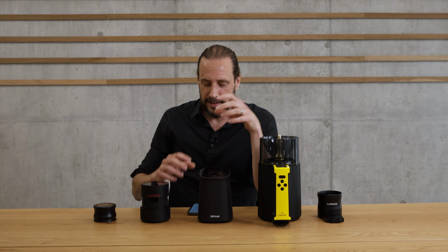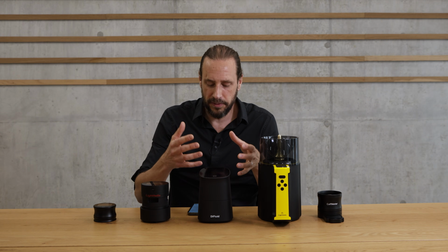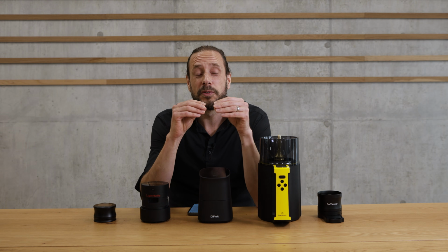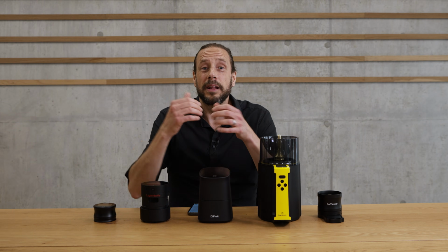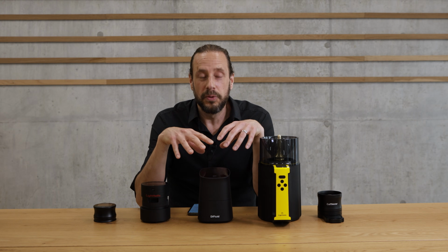What is happening here is that inside the sealed chamber, there is a small polished mirror, and an electrical cooling element chills this mirror down until water vapor builds little vapor spots on the surface, and an optical sensor measures that. Imagine cooling down a glass of water: at one point you get condensation on the outside. This happens with this mirror, and it measures the temperature where this happens, and with that it can extrapolate with algorithms the water activity of your coffee. That's a very precise and also quite fast method of measuring it, just taking a couple of seconds, and this is the way you measure in the OMIX Plus device.